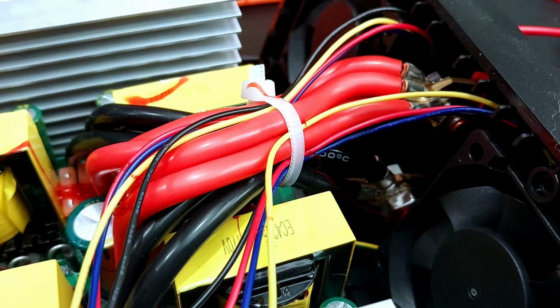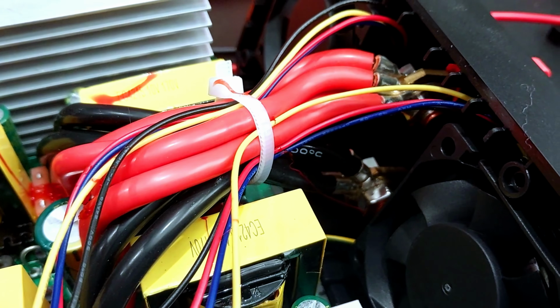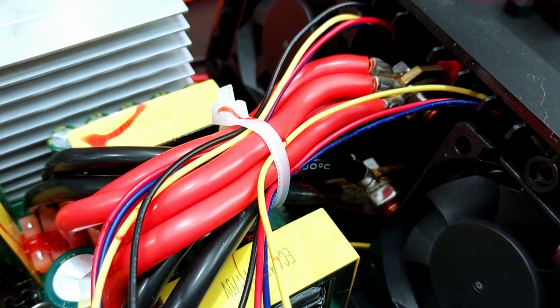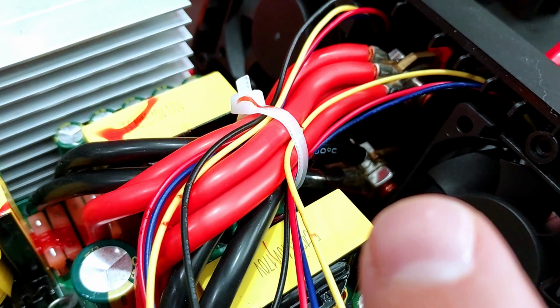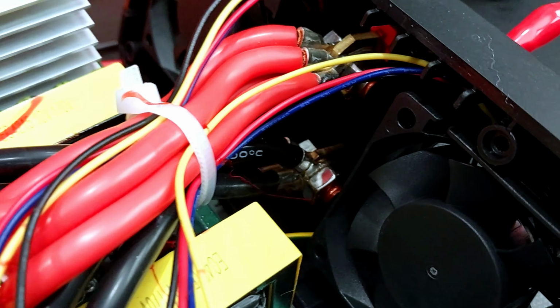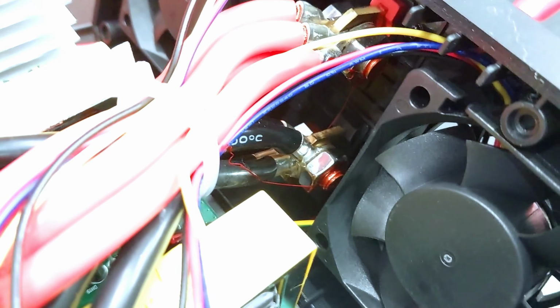What else to comment on here? The DC inlet wires - we have 3 8-gauge for positive, 3 for negative. They're bolted to the bus bar that goes to the outside for the DC input. You can kind of see it down in there. There is Loctite on those bolts, so that is good.